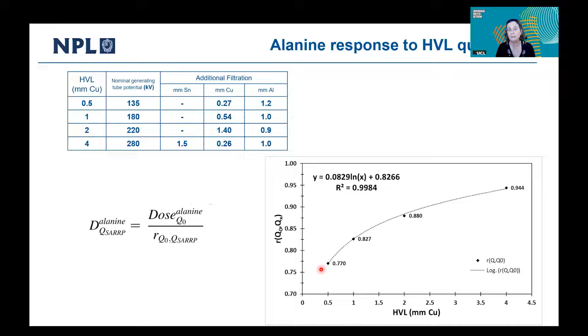As a result of this experimental characterization, a quality-dependent correction factor to the reported dose, at the quality in which these alanine detectors are calibrated, which in this case is cobalt, was found. This factor is shown here, and the fitting to that dependence is shown in the graph. It is important to note that in our work, we are reporting the quality of medium energy beams in terms of their half value layer, or HVL, in millimeters of copper.